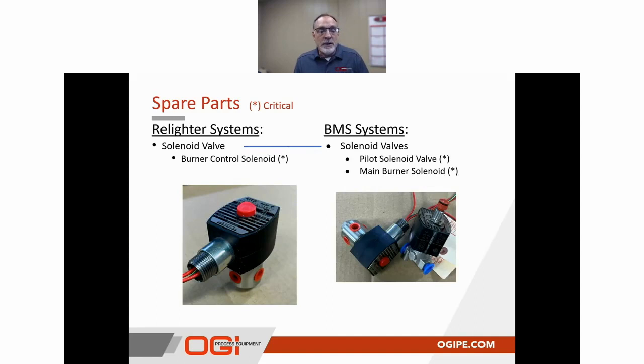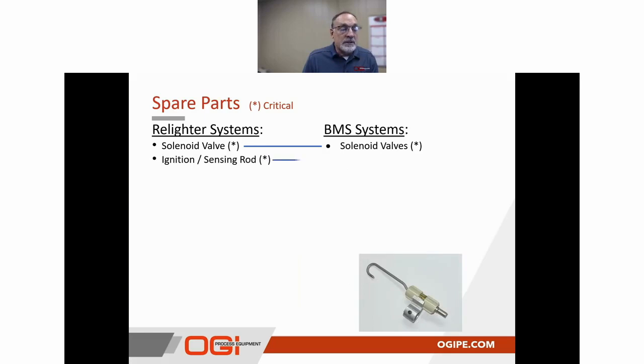First, we want to talk about the solenoid valves. On the relighter system, there's a burner control solenoid, and it's a single solenoid system. On BMS systems, typically there's a pilot solenoid that enables and disables the pilot based on safety conditions that aren't satisfied, or maybe a loss of flame, and then, of course, the main burner solenoid. There are a lot of similarities between the main burner solenoid and the relighter's burner control solenoid, based on the type of system we're talking about, whether it's pneumatic or electric, as far as how the BMS is being employed.